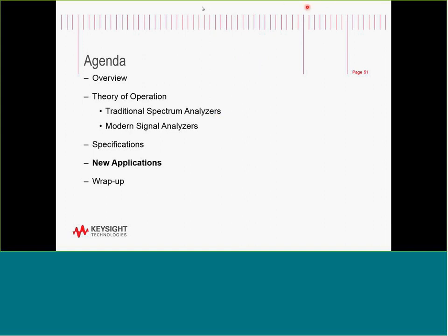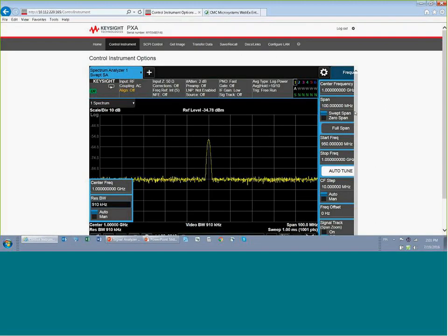What's that last display that you showed, Andre? You said you can share that display. This is the remote connection. You can share that display with your colleagues. Does that mean that if multiple people connect to the same IP address, they would all have live control of the instrument, or would one person be in control and the other people observers? Yeah, that's the thing. I never tried to have more than two. If I connect remotely, I can control it from my PC, and the person in front of the equipment can also control it. I never tried to connect two persons to the same instrument. That will be something I need to try.